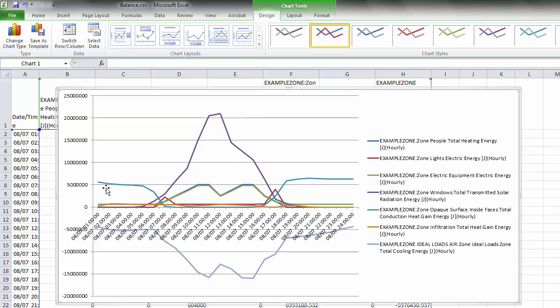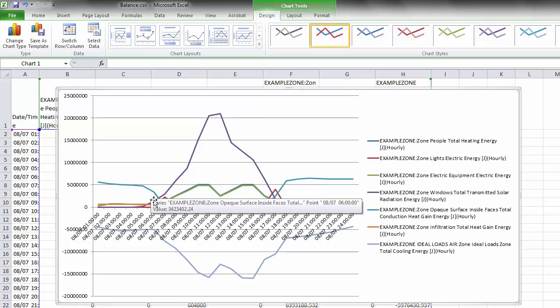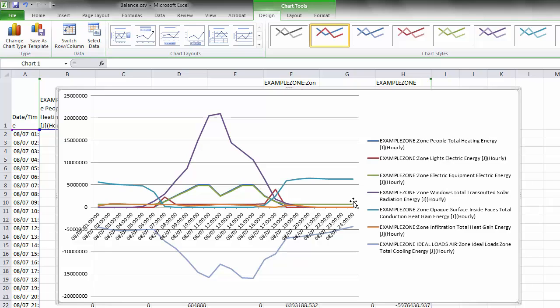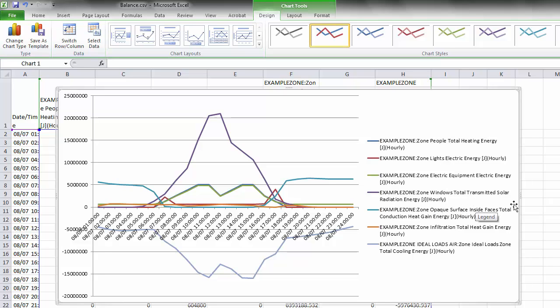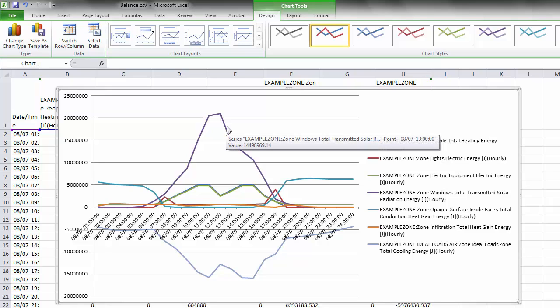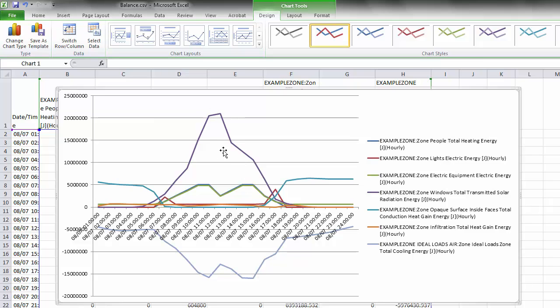Visualizing these hourly results for August 7th, there are lines on the positive side of the graph and one line on the negative side representing the cooling energy needed to maintain 26 degrees Celsius. You can see various heat gains from opaque surface conduction, people energy, and equipment electric energy following the occupancy schedule. Most importantly, there is one large peak corresponding to the zone windows total transmitted solar radiation energy in joules. This is the major contributor of heat gains, which is why cooling peaks during midday. Some solar radiation is absorbed by thermal mass, but this energy is a major contributor to the overheating we identified.